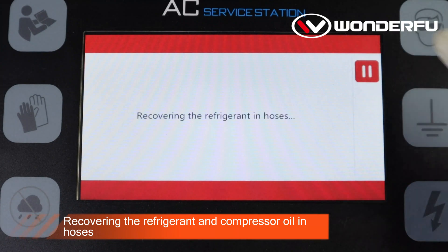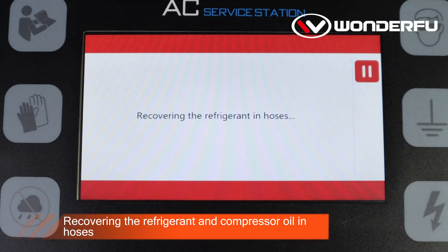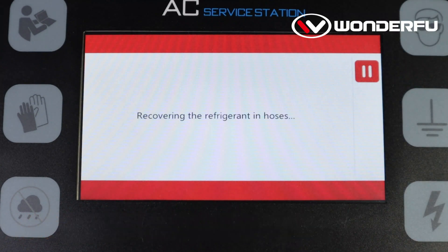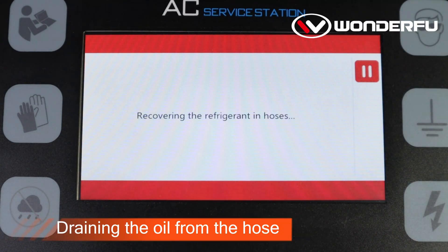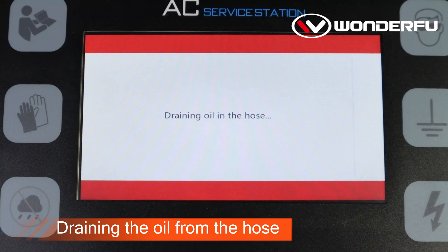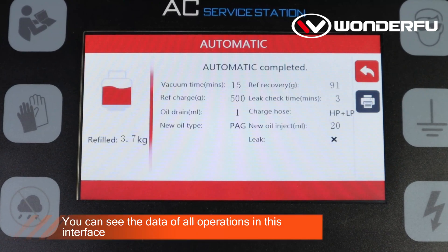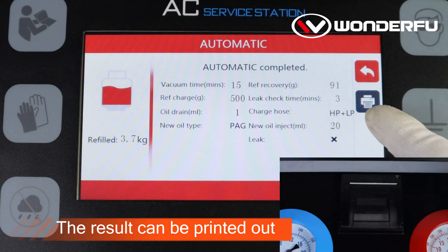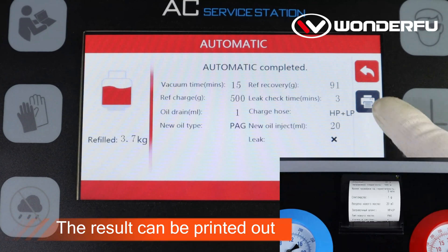Recovering the refrigerant and compressor oil in hoses. Draining the oil from the hose. Automatic operation completed — you can see the data of all operations in this interface. The result can be printed out.